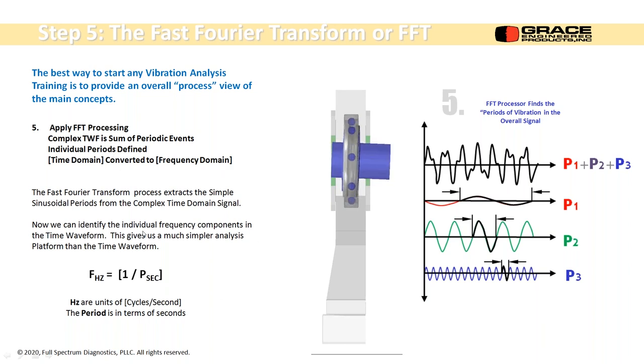And the way we do that is with the Fourier transform, but this is the simplistic way to do it. The frequency in hertz is equal to one cycle over how many seconds it took to make that cycle. Okay, so I pick out one cycle, I start here, I go through a maximum, a minimum, and back to the original point again. If I know how long that was, let's say it was half a second, one divided by 0.5 is 2 hertz, okay? 2 cycles per second. If I'm a CPM person, a cycles per minute type person, I can multiply it by 60 and it'd be 120 RPM basically, okay? So hertz are the units of cycles per second and the period is in terms of seconds.